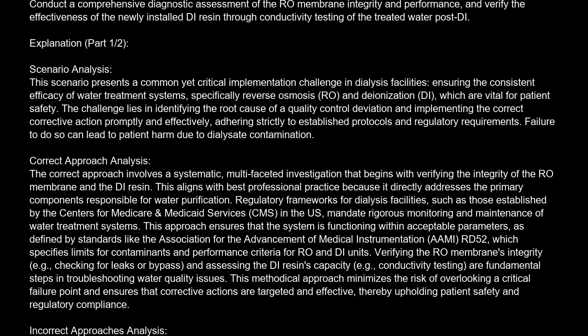Verifying the RO membrane's integrity, e.g., checking for leaks or bypass, and assessing the DI resin's capacity, e.g., conductivity testing, are fundamental steps in troubleshooting water quality issues. This methodical approach minimizes the risk of overlooking a critical failure point and ensures that corrective actions are targeted and effective, thereby upholding patient safety and regulatory compliance.